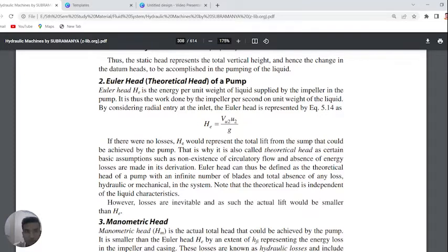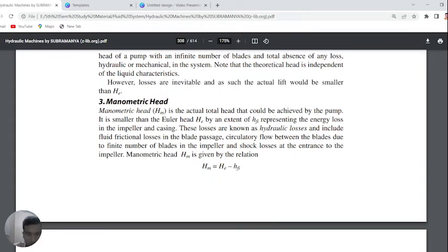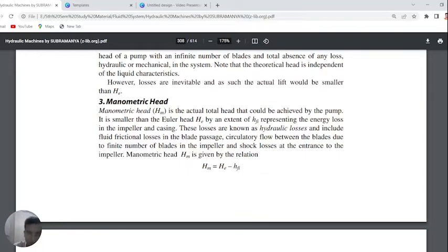Euler head is the theoretical head of a pump. The formula of Euler head is Vu2·U2 / g. Euler head is basically energy per unit weight of liquid supplied by the impeller — with mass M in numerator and Mg in denominator, M cancels and we get the Euler head formula. Manometric head is the actual total head achieved by the pump — it equals the Euler head minus the energy losses due to casing and other losses in the pump.